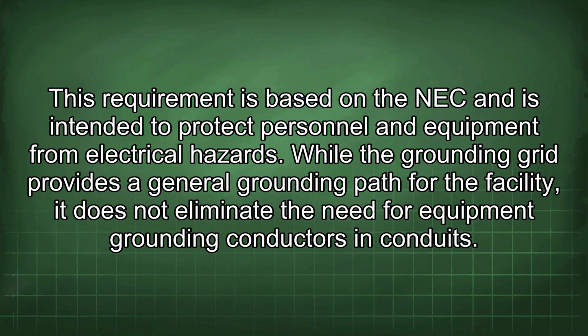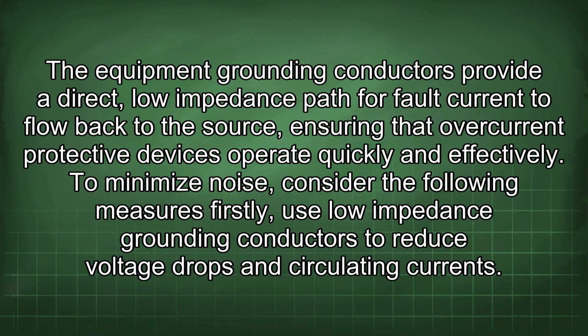While the grounding grid provides a general grounding path for the facility, it does not eliminate the need for equipment grounding conductors in conduits. The equipment grounding conductors provide a direct, low-impedance path for fault current to flow back to the source, ensuring that overcurrent protective devices operate quickly and effectively. To minimize noise, consider the following measures.